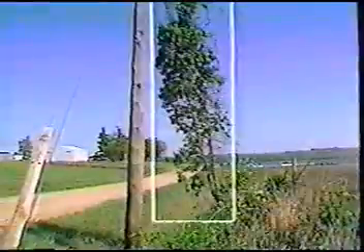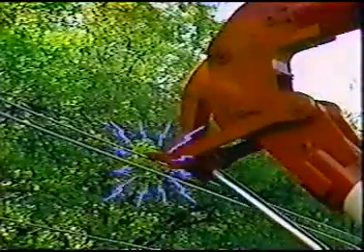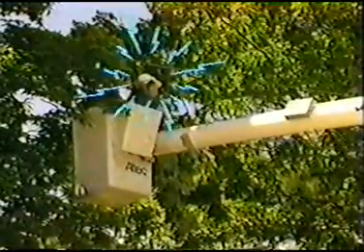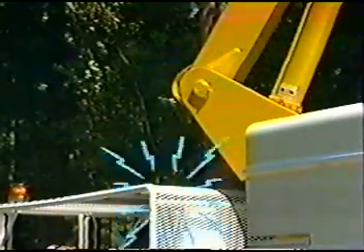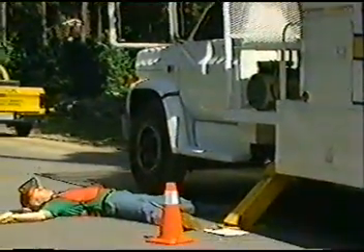Contact between a conductor and a guy wire, as a result of a vine growing into both, or even contact by an uninsulated boom, can complete a circuit. Remember, even an insulator in a boom can fail as a result of dirt contamination or delamination. If such contact occurs, the whole unit can become energized, in which case it is not only the person aloft who is vulnerable. When the circuit is completed, a ground person touching any part of this equipment and the ground at the same time would receive an electric shock by indirect contact.